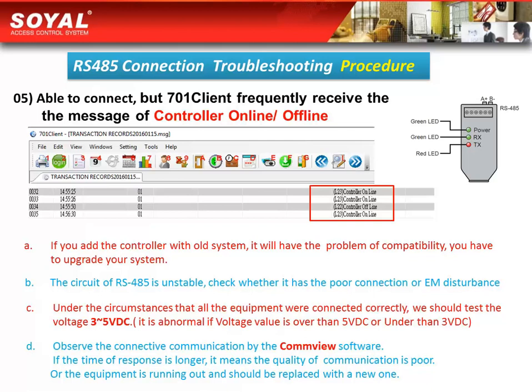Second, the RS485 circuit is unstable — check whether there is a poor connection or electromagnetic disturbance. Third, under the circumstance that all equipment is connected correctly, test the voltage, which should be 3 to 5 volts DC. It is abnormal if the voltage value is over 5 volts DC or under 3 volts DC. Fourth, observe the communication connection using the Commview software. If the response time is too long, it means the quality of communication is poor, or the equipment is worn out and should be replaced with a new one.